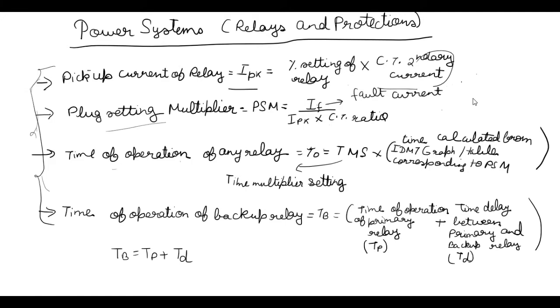Then time of operation of any relay is equal to T0, which is equal to TMS, which is time multiplier setting, into time calculated from IDMT graph or table corresponding to PSM. Now what is this? This was very difficult for me to understand, but we will see everything in the question. Now time of operation of backup relay, TB...